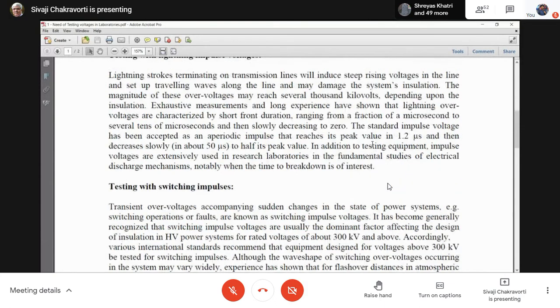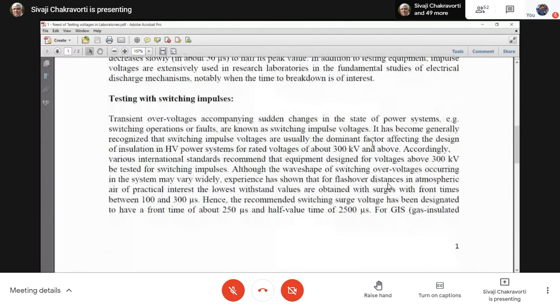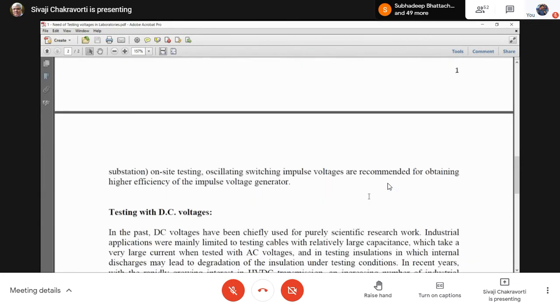Then we have the switching impulses. Switching generates two types of over voltages. One is at the lower frequency, the other is at a higher frequency. The higher frequencies are called switching impulse. These have a different wave shape than the lightning impulse, and therefore the generation of switching impulse is slightly different from the lightning impulse. So that will also be part of your course.